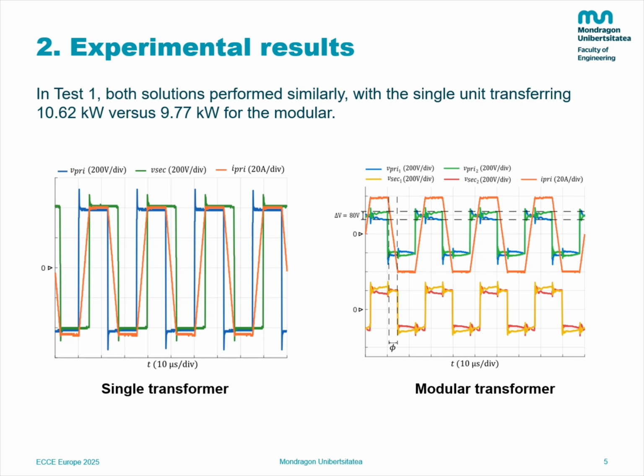Here, in test 1, both solutions performed similarly, with the single unit transferring 10.62 kilowatts versus 9.77 kilowatts for the modular. This power difference is strictly related to the different leakage inductance values presented before. In the case of the single transformer, it's 42.3 microhenries, whereas in the modular transformer it is 46.77. The figures show the experimental waveforms of the single and modular transformer at test 1. In the left, the primary and secondary side AC voltages and the primary side current are shown. In the right, the same parameters are shown, but considering that due to the series connection, the AC voltages are shared between each module.